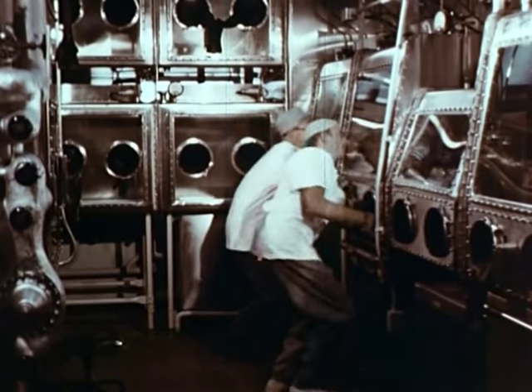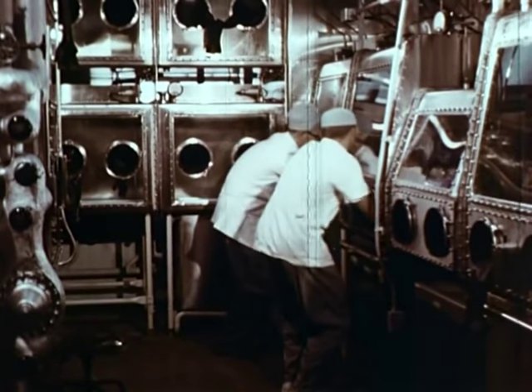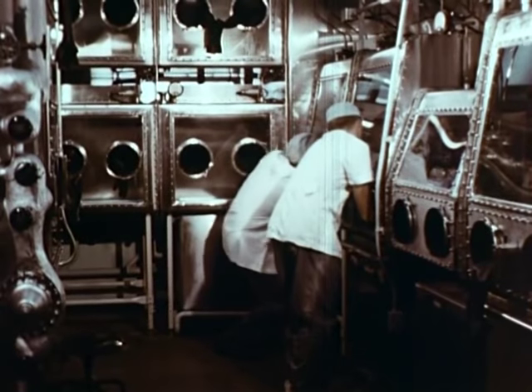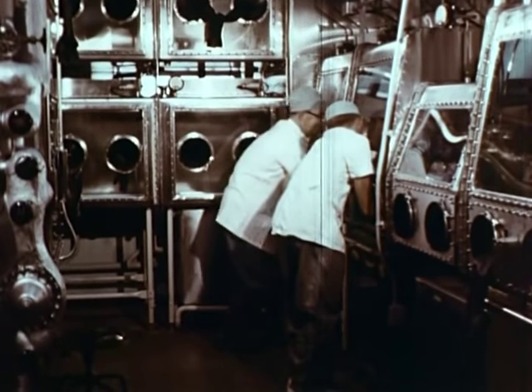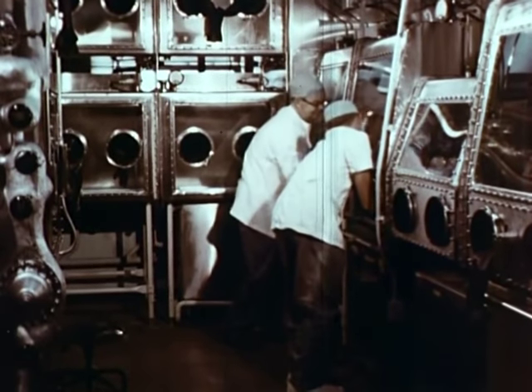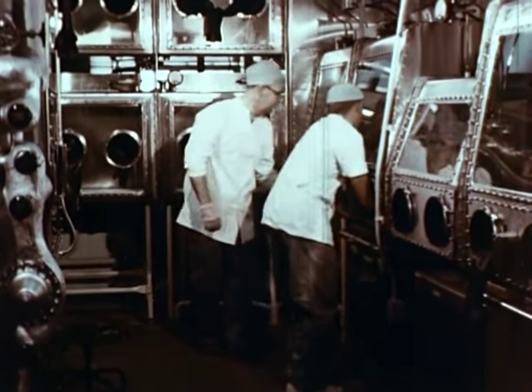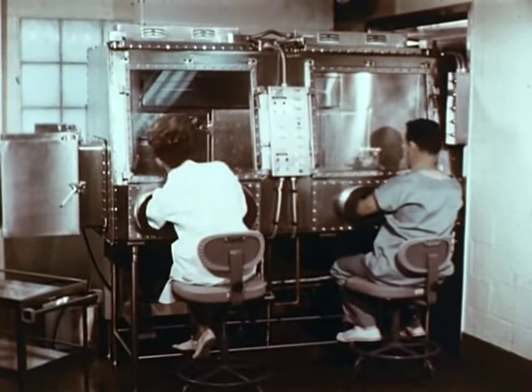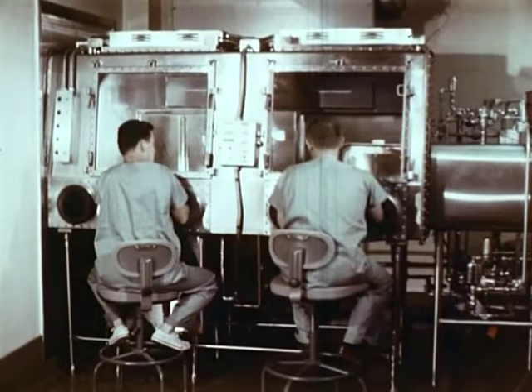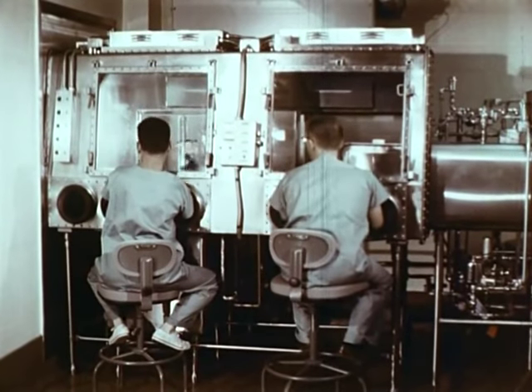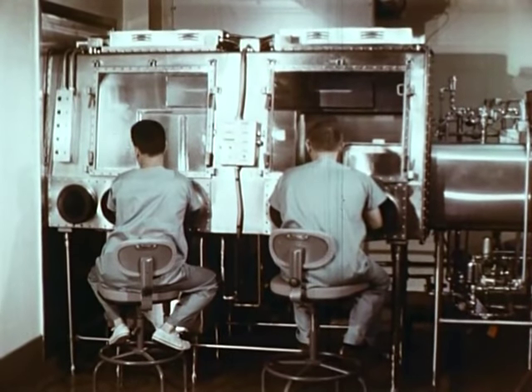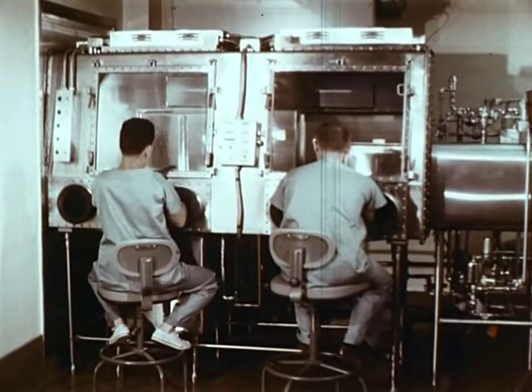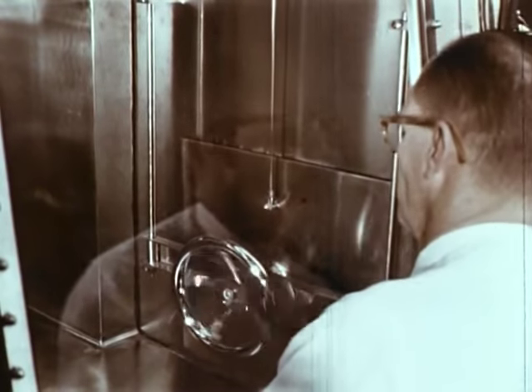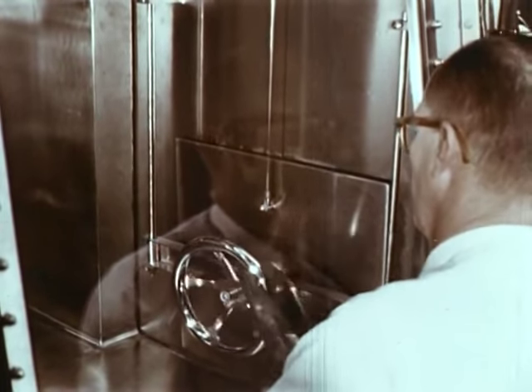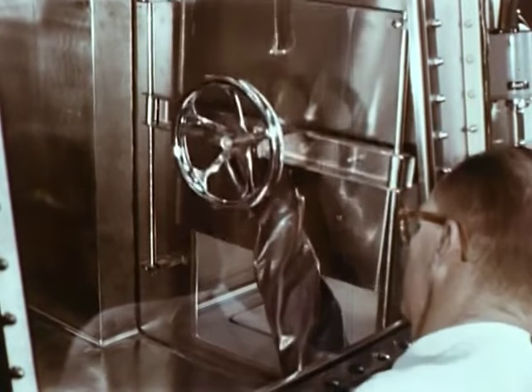These gas-tight cabinet systems can vary widely in arrangement. Maximum utilization of floor area can be achieved by double-stacking the cabinets and placing them around the walls. Others might be straight line units that extend through a wall. This particular design speeds up workflow between two separate rooms. The possible internal features for absolute barrier systems are almost limitless.